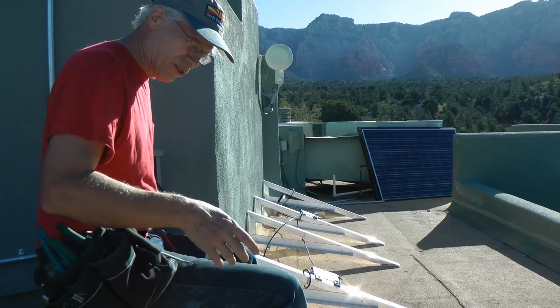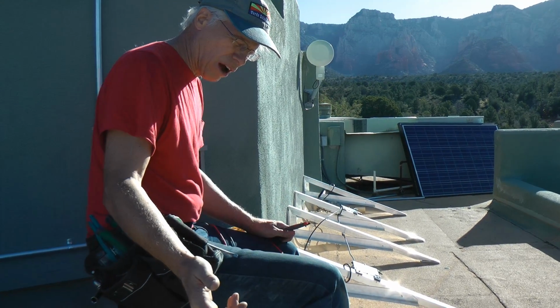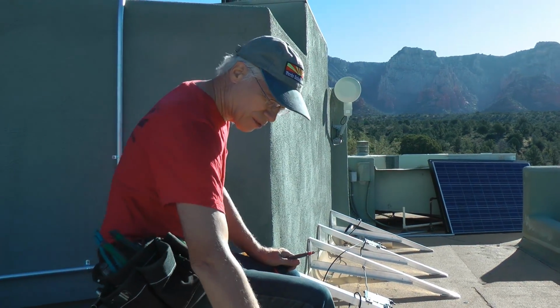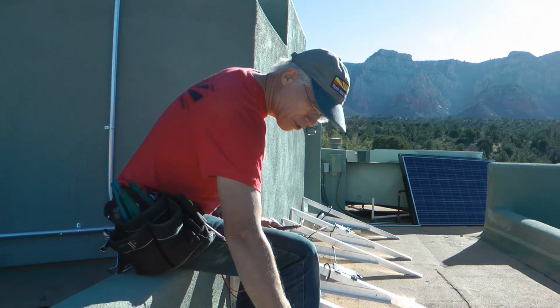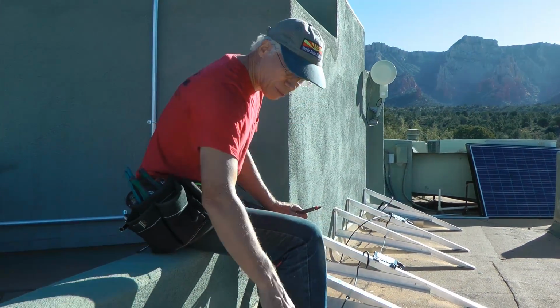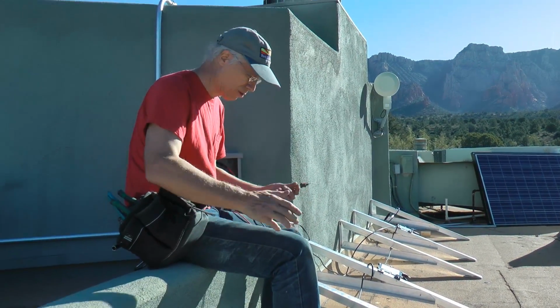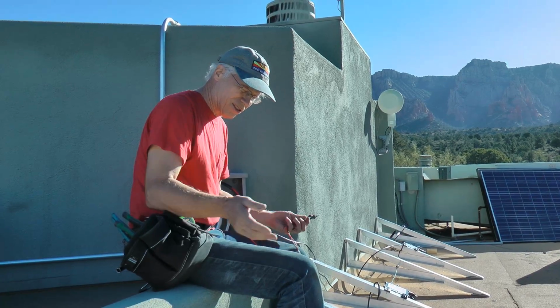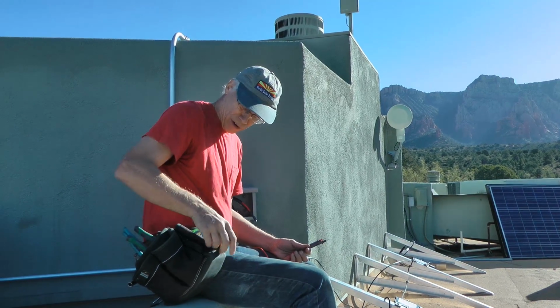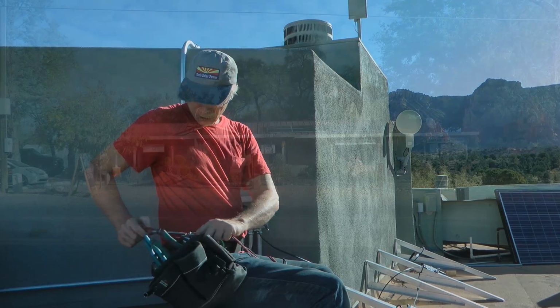Another benefit is that when the system is off, the module, what SolarEdge calls the power box or power optimizer, turns off. So the system is a lot safer as a result, if a fireman or emergency people or anybody was ever up here working on the system. When the system's turned off, the panels are off.